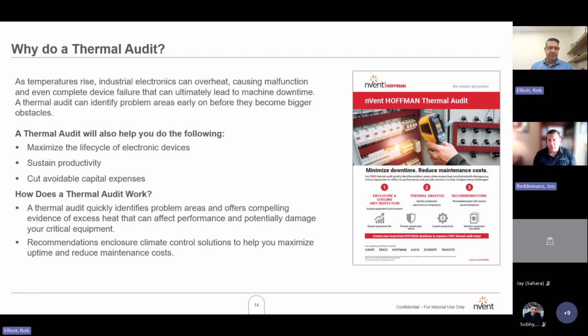We go into a facility and really what we're looking for is the enclosure size, what the ambient temperature is, and what that enclosure temperature is while the process is running. We're looking for the difference of internal temperature versus ambient temperature. Through the selection process, we can estimate how much heat is being produced and come up with a potential cooling solution. To Rob's point earlier, not everything needs an air conditioner. We may simply be able to use plant air and push it through the system to very cost-effectively manage that thermal load for that application.